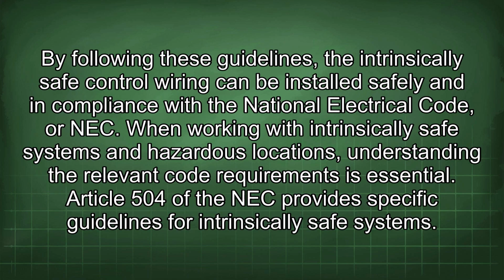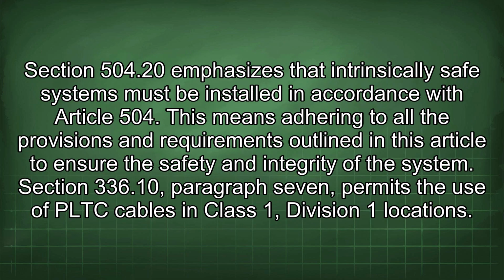By following these guidelines, the intrinsically safe control wiring can be installed safely and in compliance with the National Electrical Code, or NEC. When working with intrinsically safe systems and hazardous locations, understanding the relevant code requirements is essential. Article 504 of the NEC provides specific guidelines for intrinsically safe systems. Section 504.20 emphasizes that intrinsically safe systems must be installed in accordance with Article 504. This means adhering to all the provisions and requirements outlined in this article to ensure the safety and integrity of the system.